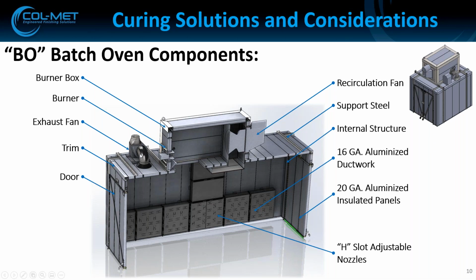Another important thing to notice is that we do have an independent exhaust fan. We have a recirculation fan. Then not pictured here, well, actually the burner, and the burner also has a small combustion fan. Always important to make sure that you're getting clean air coming into the combustion area. If you're drawing in powder or a lot of dirt, you're going to damage the burner. It's going to get contaminated, and then it cascades into more complex problems from there. But this gives you a good overall view. A good thing to remember about the BO series oven is that the ductwork is in the side, and then the airflow moves through the sides up towards the top and then is recirculated through the oven.